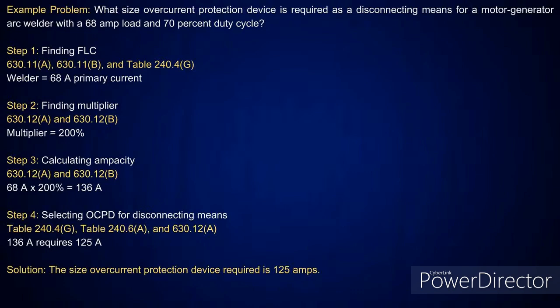Now, the one we did before was non-motor. This is a motor generator type. We're just going to show you doing it without doing the conductor first, because I can already tell you which is going to be the largest. It's going to be taking the 200%. The reason we did that one before is to show you we took the conductor and got the amperage, took it at 200%, and it matched up exactly when we dropped down. That proves everything we're teaching you.